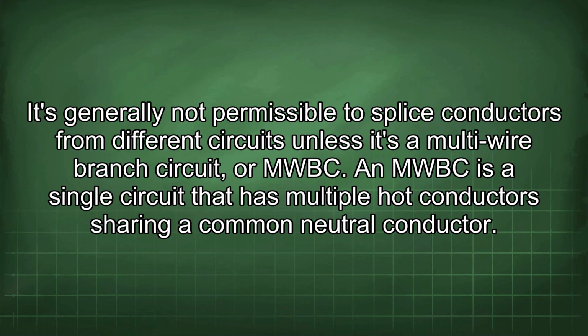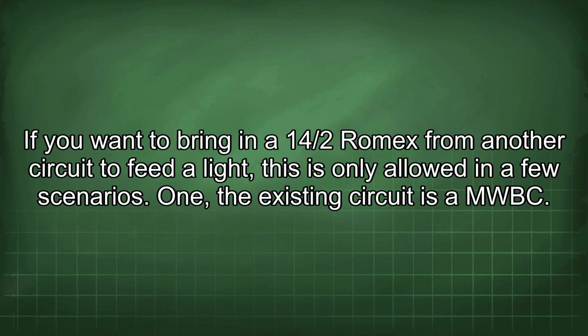It's generally not permissible to splice conductors from different circuits unless it's a multi-wire branch circuit, or MWBC. An MWBC is a single circuit that has multiple hot conductors sharing a common neutral conductor. If you want to bring in a 14/2 Romex from another circuit to feed a light, this is only allowed in a few scenarios. 1.